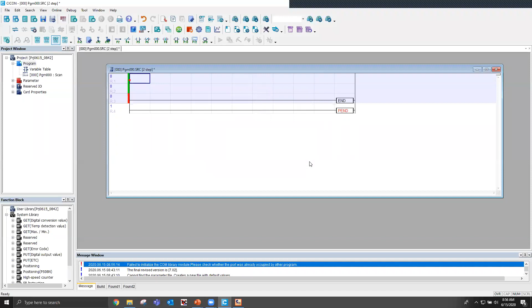So if I go to D device right here. When I talk about double word, remember we're in the D registers, so we're no longer talking about hexadecimal. It stops at 9 right here. Each one of these registers is a word itself. So when I talk about a double word move, I'm taking D0 and D1 and moving them down to D10 and D11. So this moves here, and then this moves here. That's what we call a double word move.